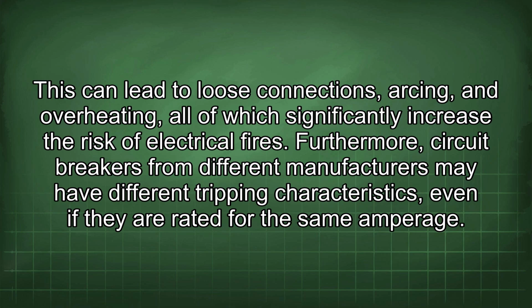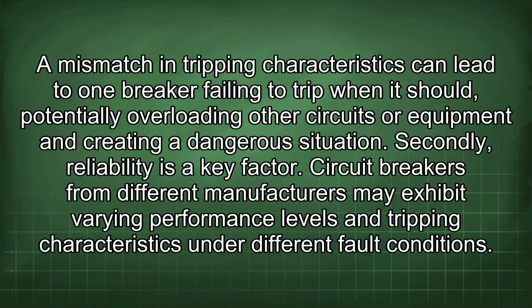Furthermore, circuit breakers from different manufacturers may have different tripping characteristics, even if they are rated for the same amperage. A mismatch in tripping characteristics can lead to one breaker failing to trip when it should, potentially overloading other circuits or equipment and creating a dangerous situation.